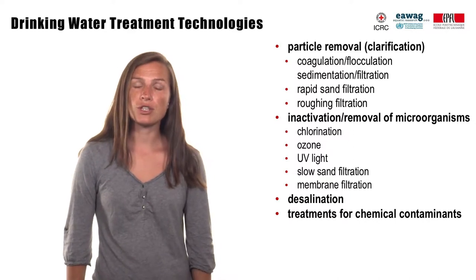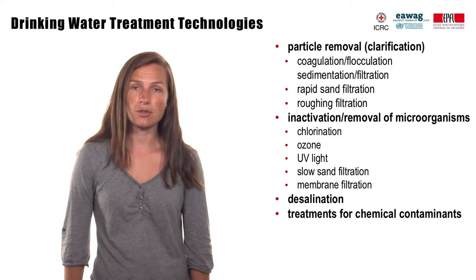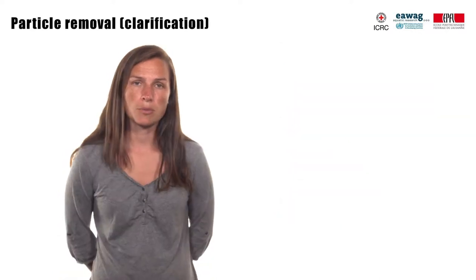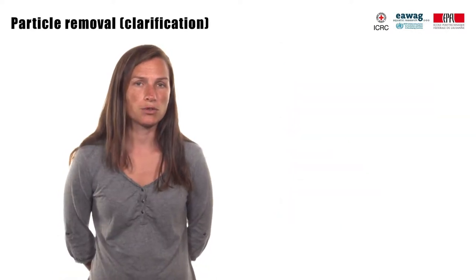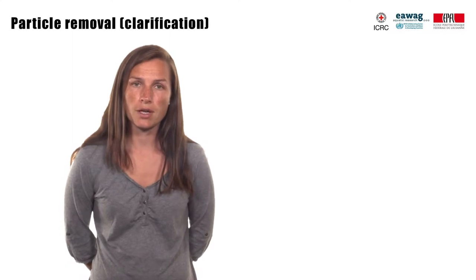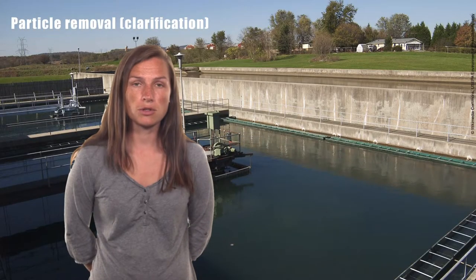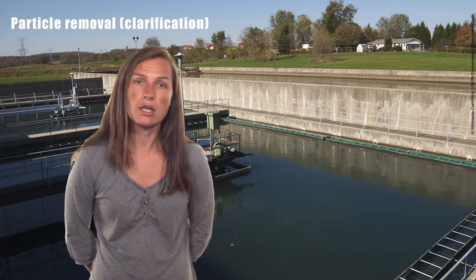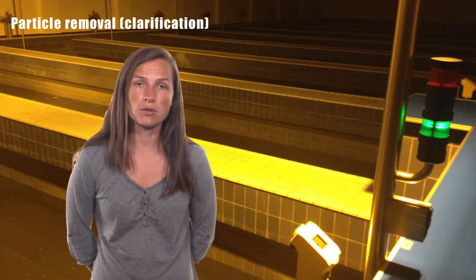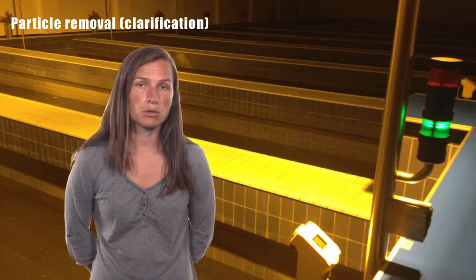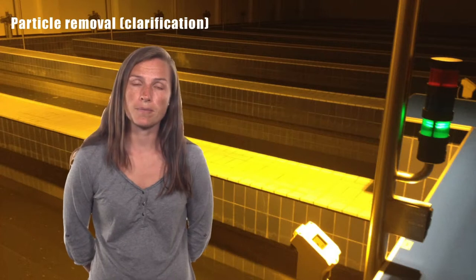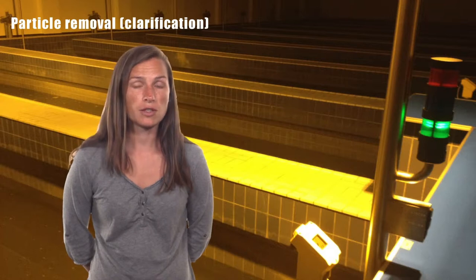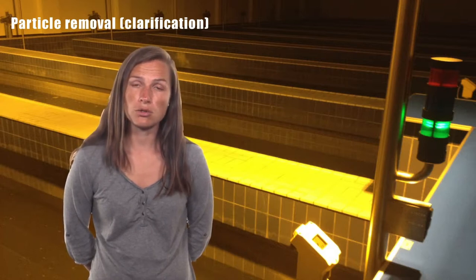A meaningful combination of technologies is in most cases necessary to achieve the WHO water quality standards for safe drinking water. The purpose of clarification is to remove as much particulate material as possible. Conventional treatment systems usually apply coagulation and flocculation combined with sedimentation or filtration. Rapid sand filtration without coagulation is used as well on large centralized drinking water treatment plants or community supplies, where roughing filtration has been used successfully as efficient and low-maintenance pretreatment.